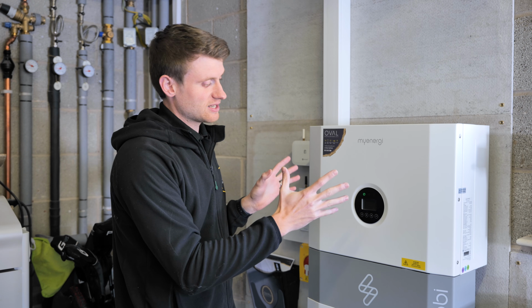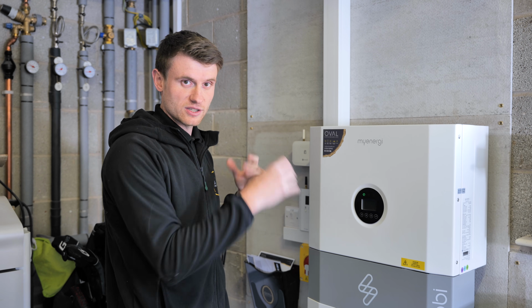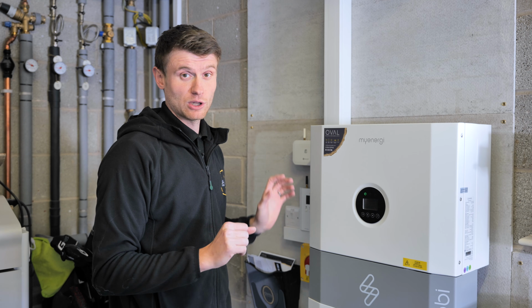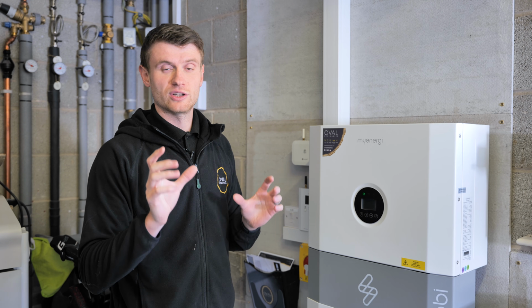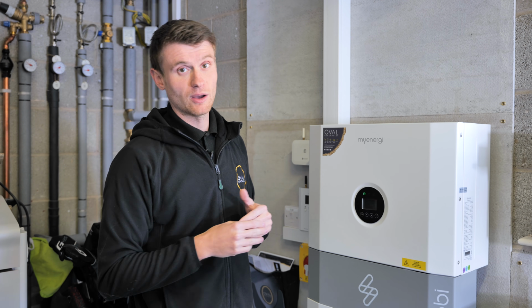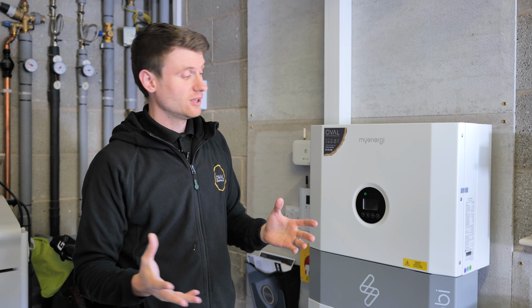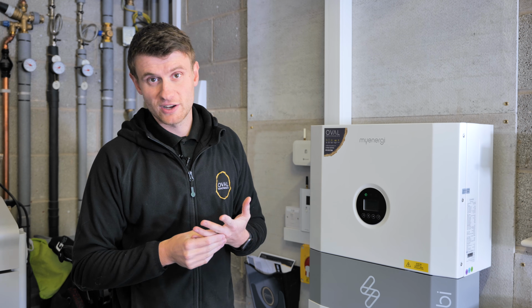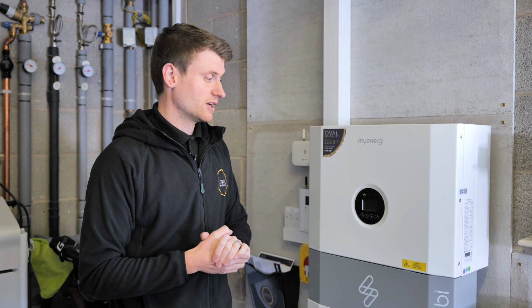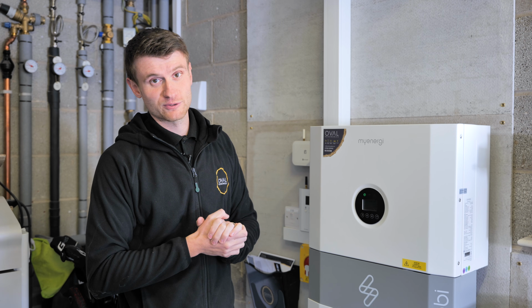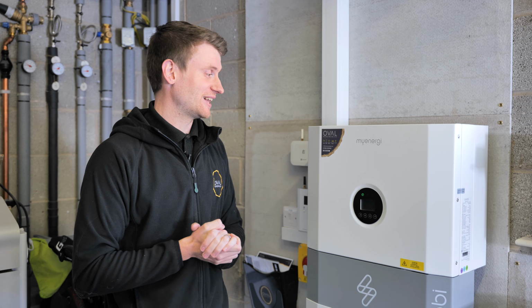So the Libbi system will always look at all the settings and the export limit that's set, to make sure it's not going to affect what the grid can handle. That's just part of getting it done professionally and getting the right approvals, because the last thing we want is a bill coming through the post for a new transformer for the local area.